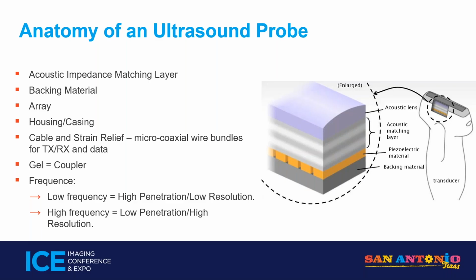The sooner you act, the better. If it's just happened in the last, say, two weeks, there's probably no internal damage to the probe, so we can quickly repair it, and it's cost effective. If you notice it and say, it's no big deal, and you wait six months to a year to get it repaired, now you've had intrusion into the electronics, into the array. Now it's not going to be repairable, and the cost is going to go way up. So again, the sooner you see damage to a probe, even if it's very minor, get it out of service, get it evaluated, and we can take care of it. It's cheaper that way. Okay.